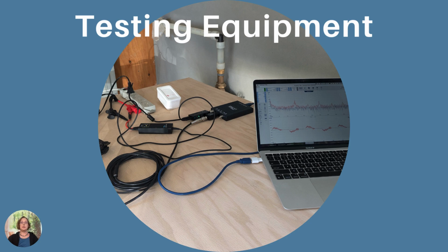In this presentation, I'll show that different inverters create different varying levels of power quality. Sometimes a simple external capacitive filter can help clean up the harmonics. Sometimes a more customized filter would be needed. I'll show these harmonics using screen captures generated by a consumer-grade oscilloscope.